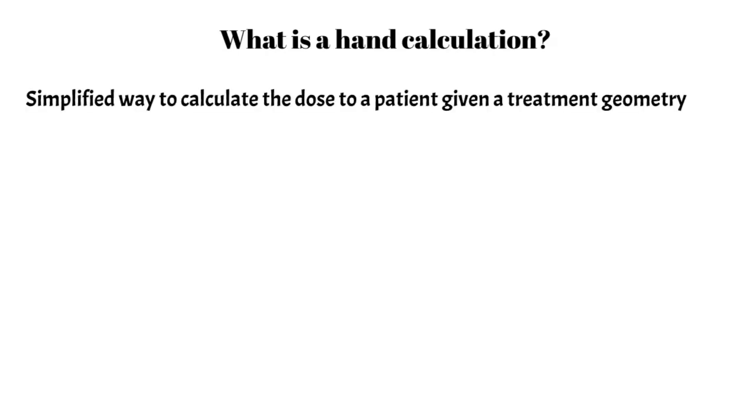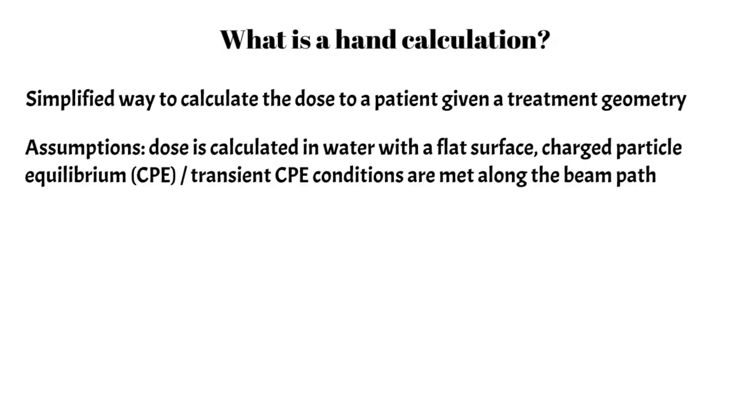In essence, it's a simplified way to calculate the dose to a patient given some arbitrary treatment geometry. The hand calc itself makes a few assumptions. One is that dose is calculated in water with a flat surface. Another is that charged particle equilibrium or transient charged particle equilibrium conditions are met along the beam path.